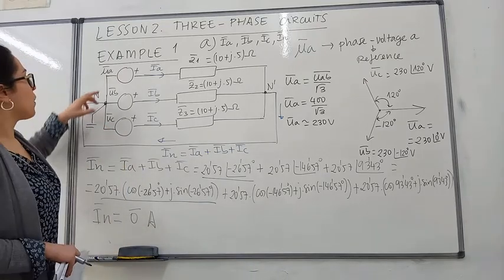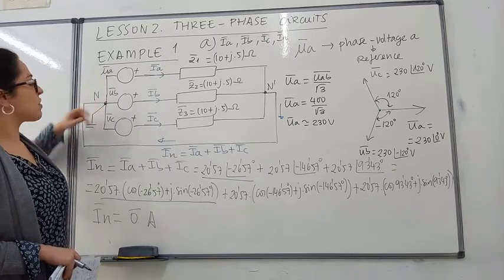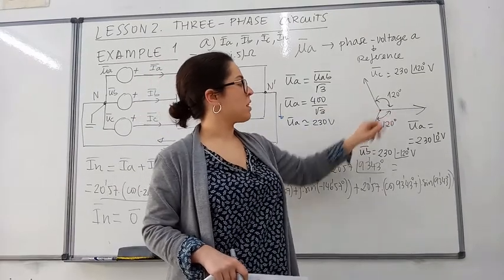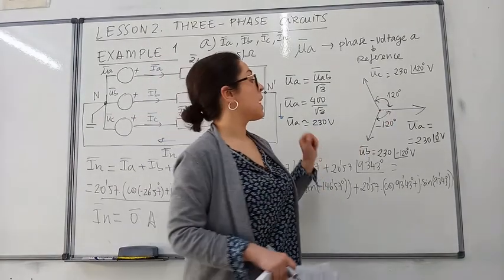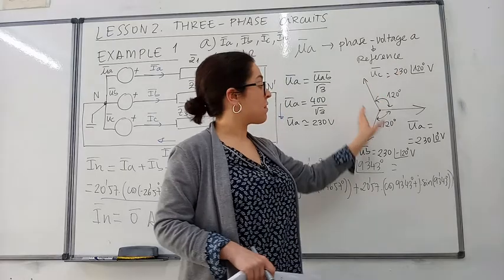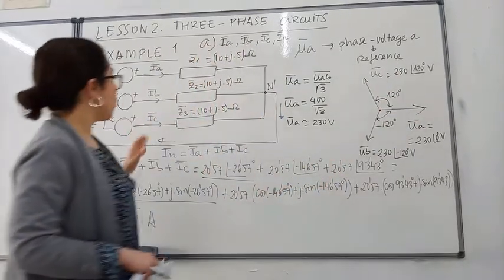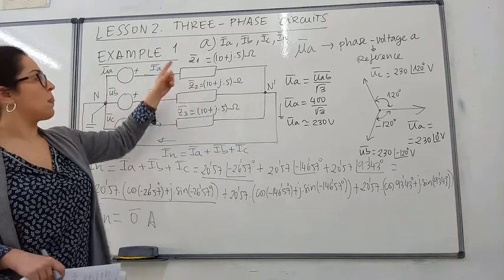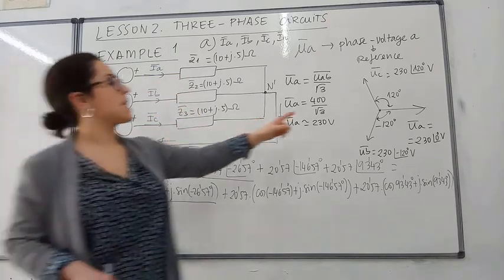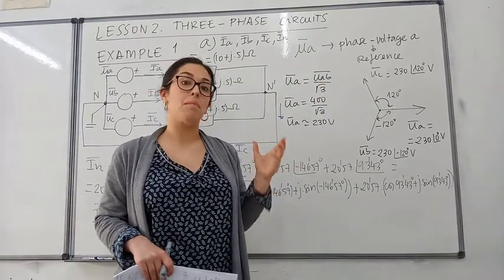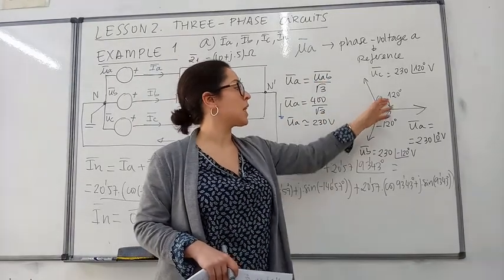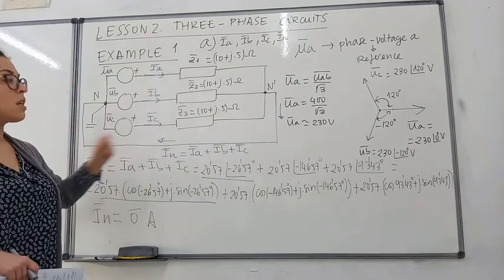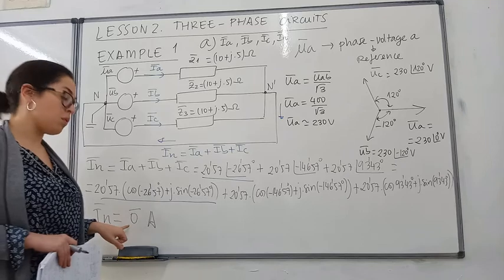That is true when we have a symmetrical system where the phase voltages are shifted 120 degrees, and also when we have a balanced load. So in that situation, when the load is balanced and the voltages are equal in absolute value and shifted 120 degrees, then the current in the neutral conductor is equal to zero.